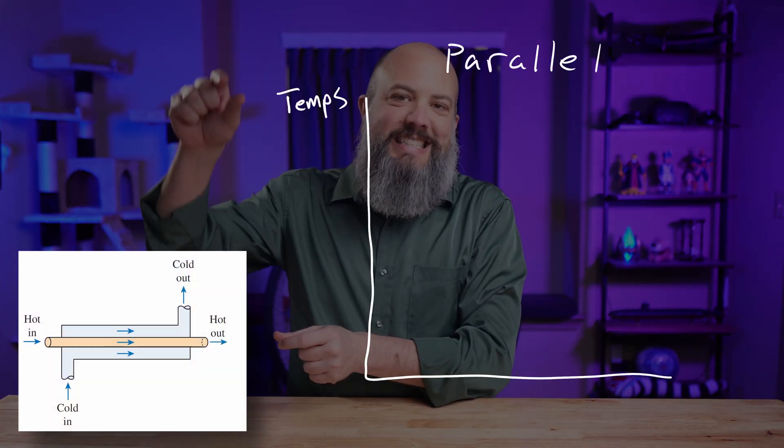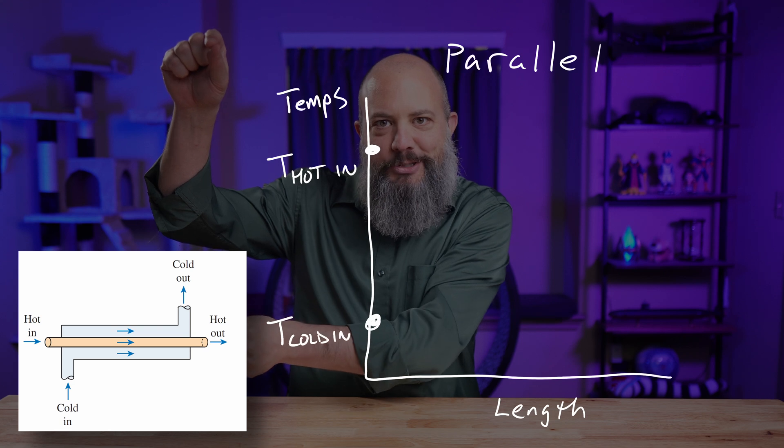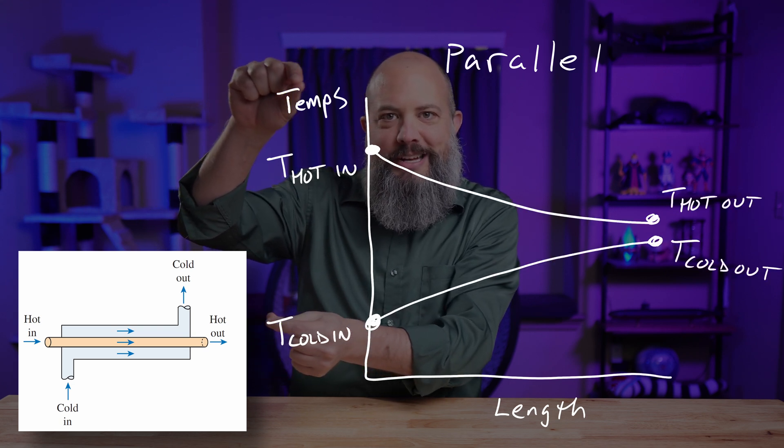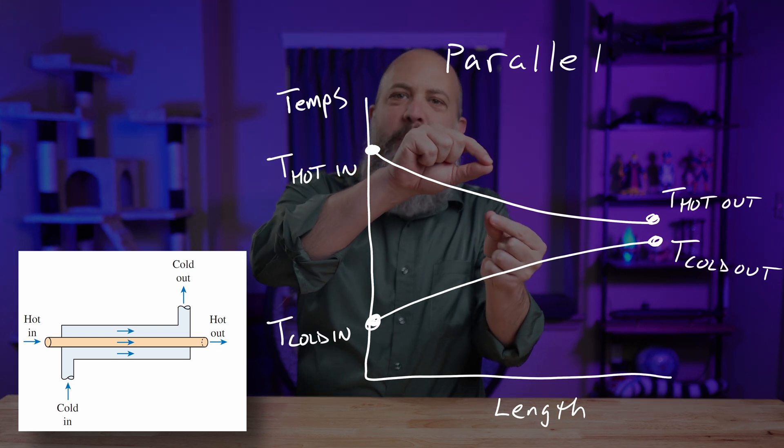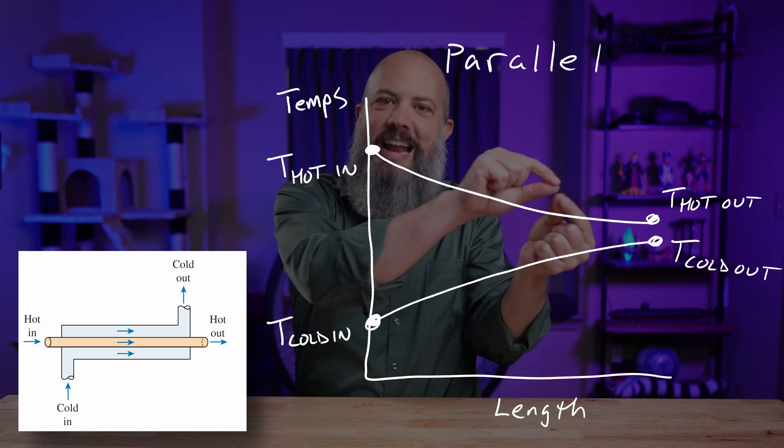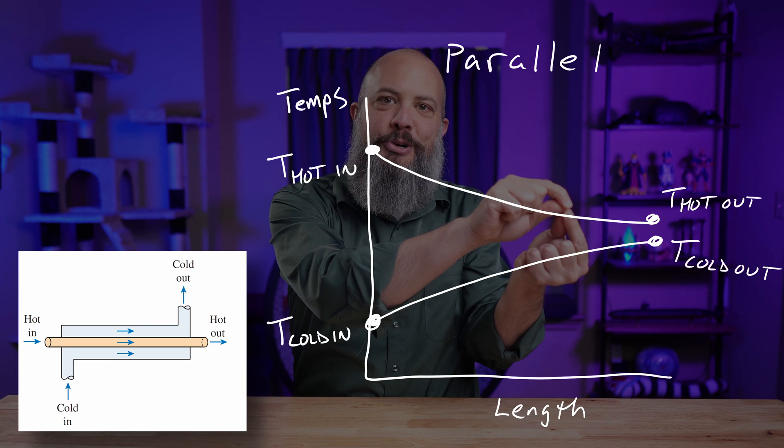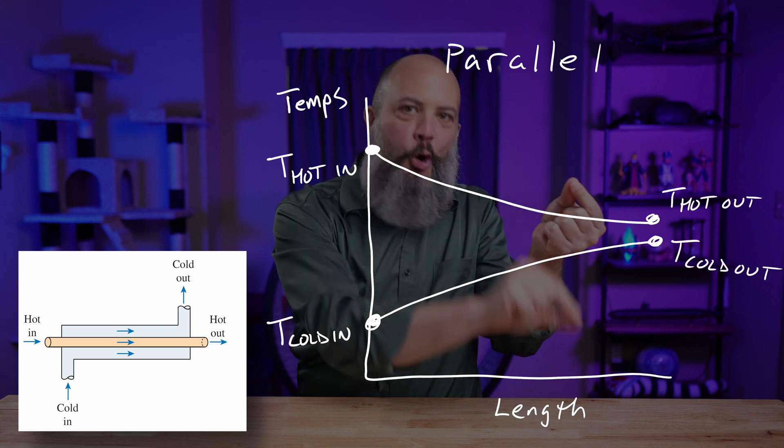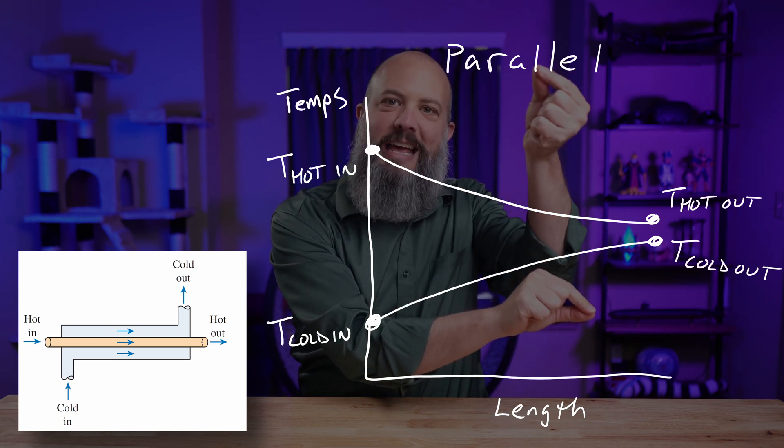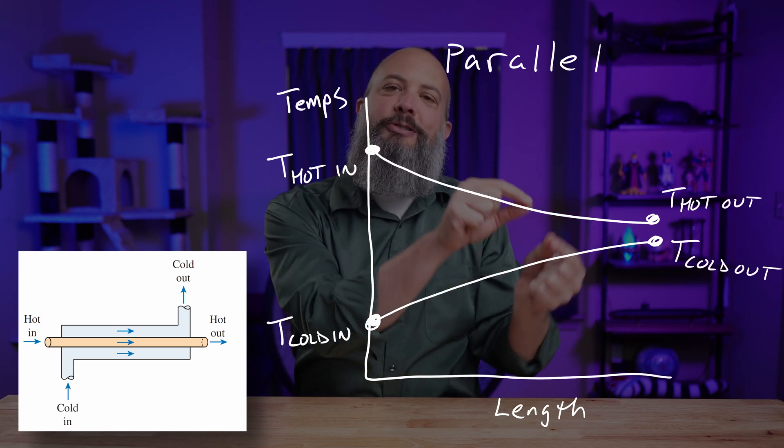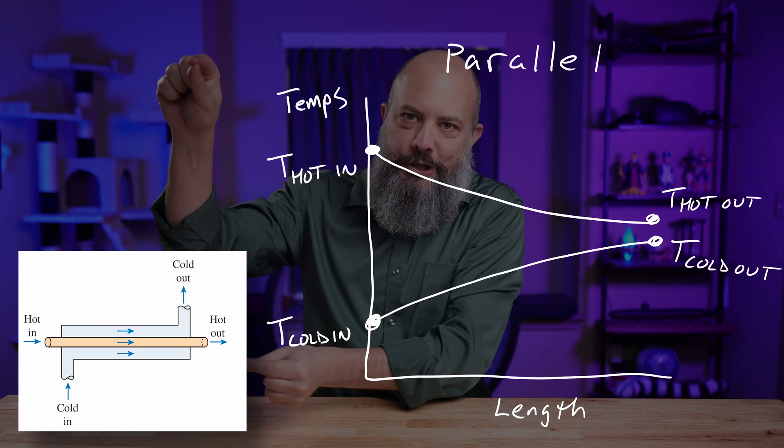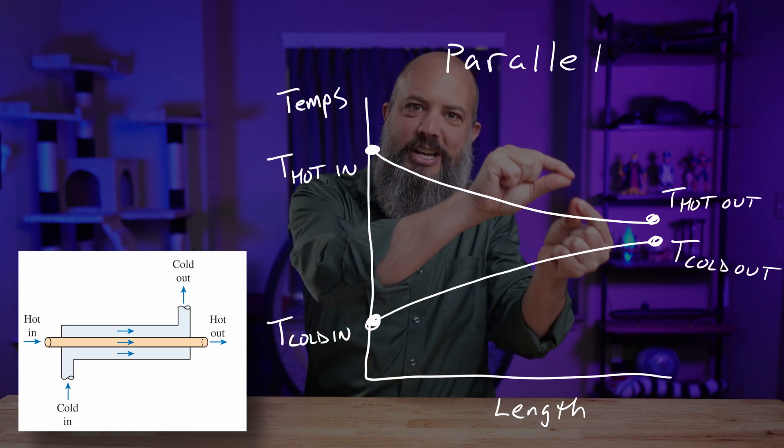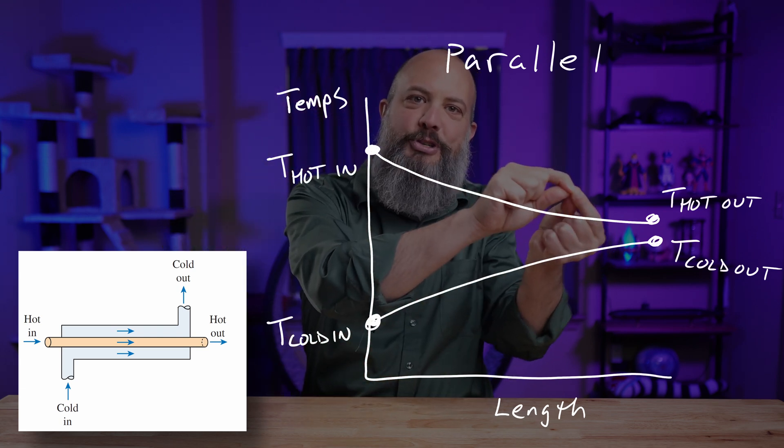In parallel flow, the steam enters really hot, water enters really cold. And as they go through the heat exchanger, the steam gets colder, the water gets warmer, and the best possible end state has them at the same temperature. The steam can never get colder than the water and the water can never get hotter than the steam. And so there's sort of a limited upside to how good a parallel flow heat exchanger can be because those exit temperatures can never cross.